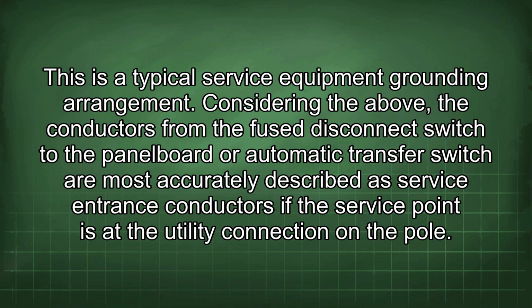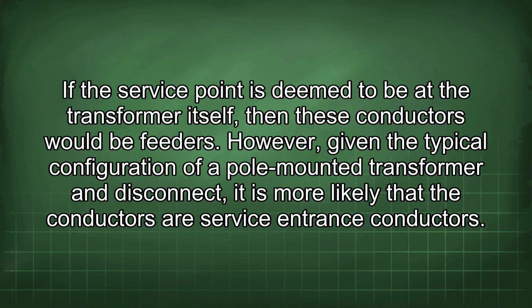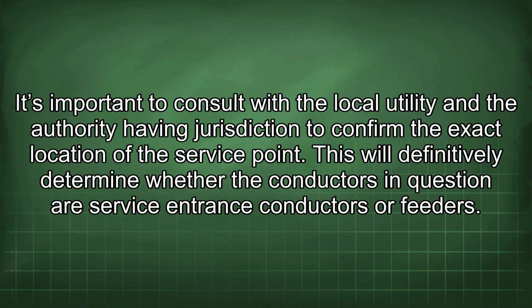Considering the above, the conductors from the fused disconnect switch to the panel board or automatic transfer switch are most accurately described as service entrance conductors if the service point is at the utility connection on the pole. If the service point is deemed to be at the transformer itself, then these conductors would be feeders. However, given the typical configuration of a pole-mounted transformer and disconnect, it is more likely that the conductors are service entrance conductors. It's important to consult with the local utility and the authority having jurisdiction to confirm the exact location of the service point. This will definitively determine whether the conductors in question are service entrance conductors or feeders.